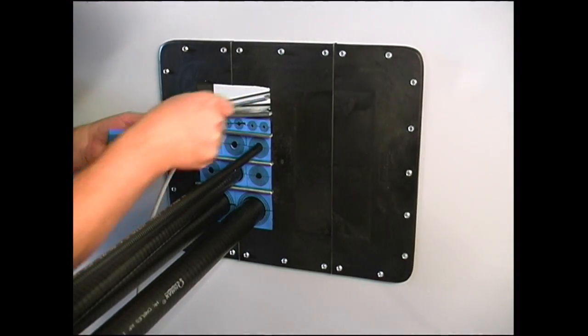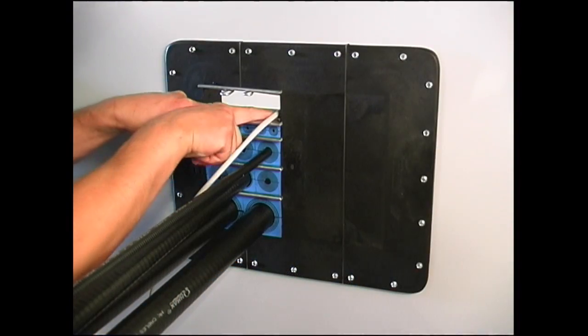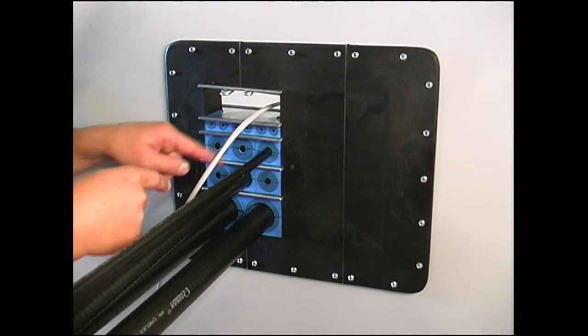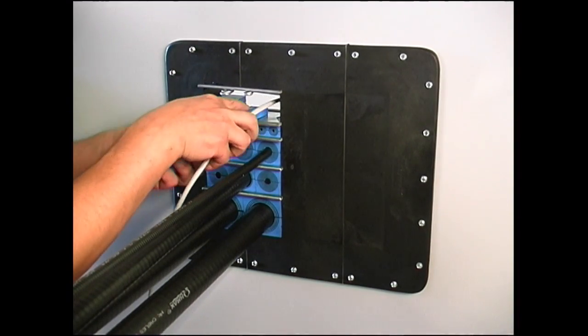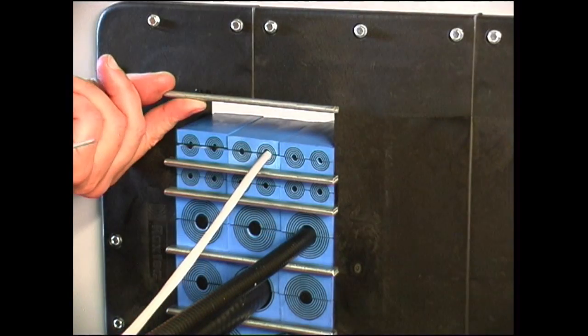Before installing the final row of modules, it is necessary to insert the two remaining stay plates. The stay plate clip provides convenient help during installation. Attach the clip below the top stay plate and it will be kept out of the way during installation. Install the final row of modules between the stay plates.